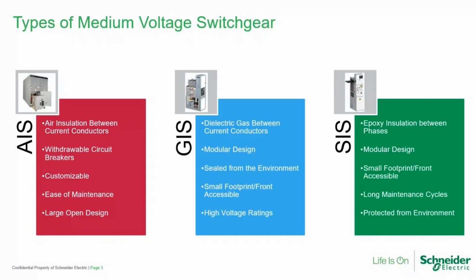Some of the benefits here are a smaller footprint, much more modular design, a sealed from the environment design, a sealed for life tank for the actual circuit breaker, and this is especially advantageous at higher voltage ratings, at that 27/38 kV class medium voltage switchgear ratings.